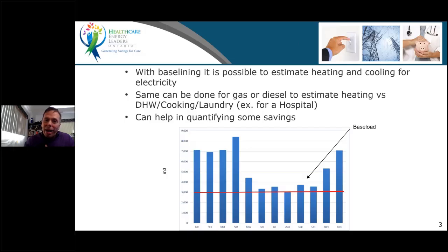The red line here that I drew is at the average of the summertime usage. And you can multiply that value, which in this case would be, it's very small, but it'd be around 3,000 cubic meters per month. Multiply that by 12, and that's your base load. Anything above that is really your heating related or your weather related consumption. So if you want to know very roughly my total gas consumption, how much goes to my base load, which is usually, like I said, kitchen, domestic hot water, obviously, and sterilization and the dryers, that will give you that split.